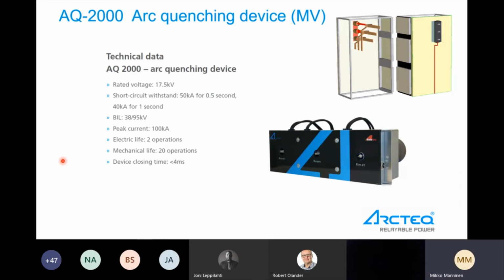Then for the medium voltage AQ2000 arc quenching device. On the top right corner, there is a medium voltage switchboard, and there is a sample of how this can be built and connected to the bus bars. So it is connected here on the side of the bus bars, and here you can see it from the other side. It is connected with copper to the existing bus bars.